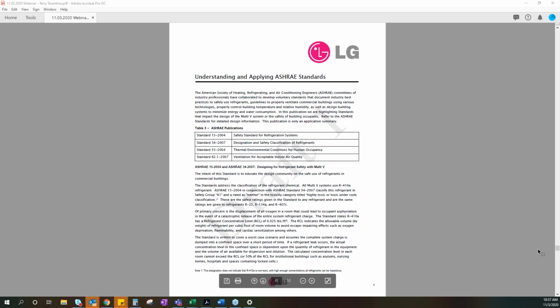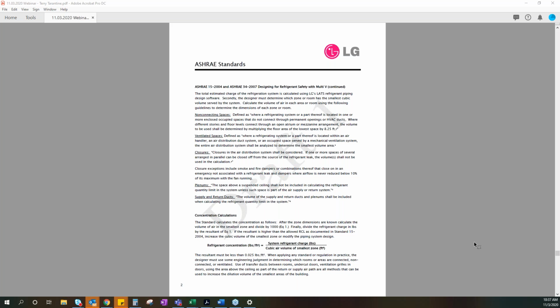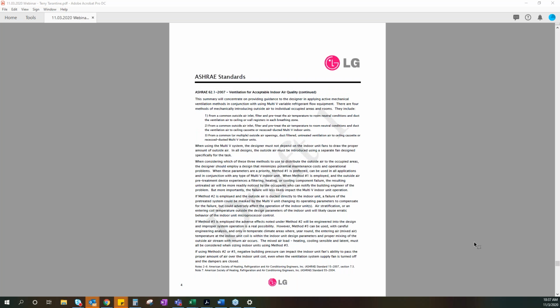And here we're talking about some ASHRAE standards, again, on the refrigerant concentration. If you are looking at a VRF system, please make sure that your designers are designing correctly for the refrigerant concentration limits. Very often as we're bidding on prints, we'll see that no attention has been paid to that, where we'll have to take maybe a 40-ton unit and break it into 20s or 10s, depending on how they've got it set out. So if you're looking at VRF, make sure that your designers are up to date on their ASHRAE standards. Just a little bit more about the different concentrations in refrigerants.